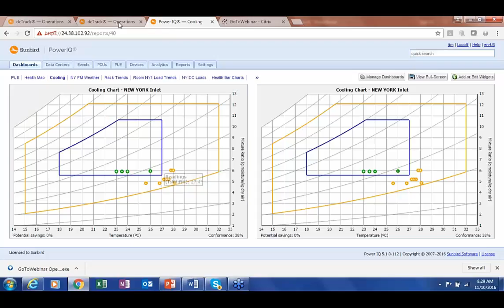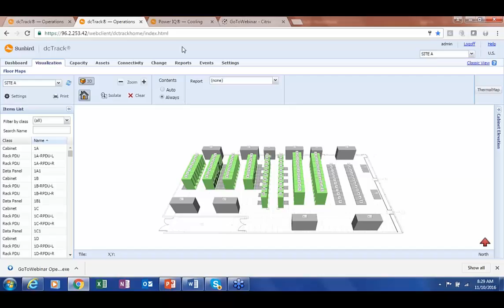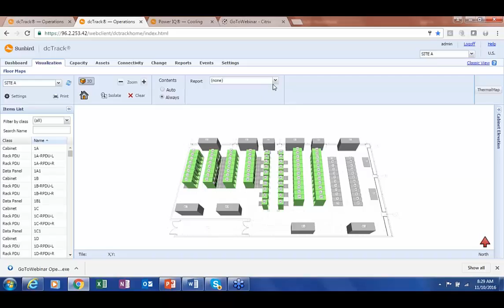Since I do have some hotspots, I want to understand my thermal parameters at a more granular level. So I look at my data center in 3D with full contents. I pull up a report that allows me to look at temperature per cabinet front, the inlet cold aisle, giving me a cabinet-by-cabinet temperature view, easy to visualize: cabinets in red are hotter than my user-configurable thresholds, cabinets in blue are colder. What I'd really like is cabinets in green, which are in the sweet spot. I apologize, these readings are in Fahrenheit, but it's easily switchable to Celsius.